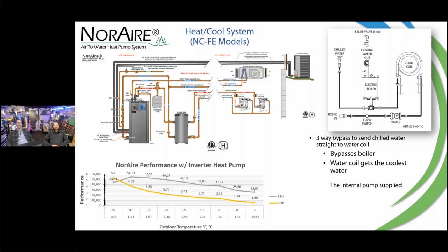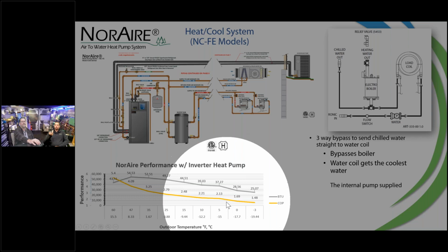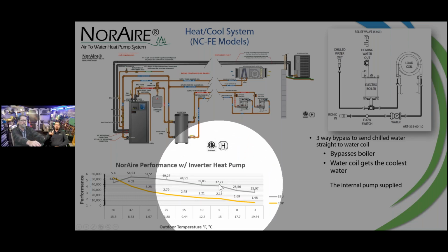And maybe, especially if you go with inverter systems, there's a good chance—and you can see here the performance at the bottom, this is based off an inverter system—just look at the numbers we get in here. When we get down to 5 degrees on an inverter, we're still getting 37,000 BTUs out of this system, right? Even 28,000 BTUs on a 0-degree day.